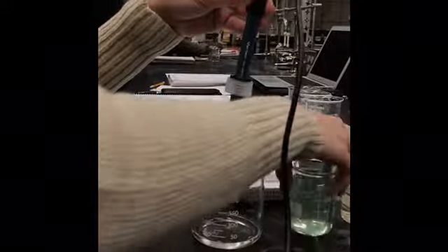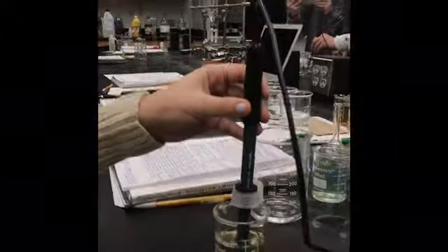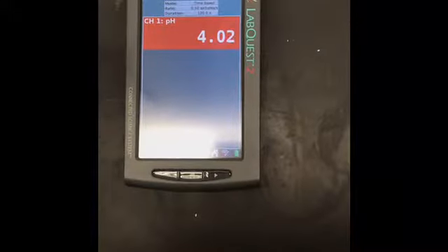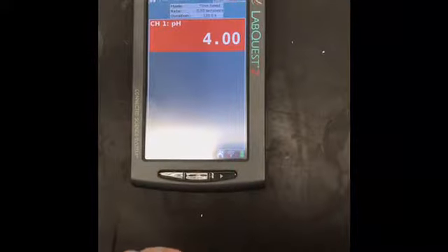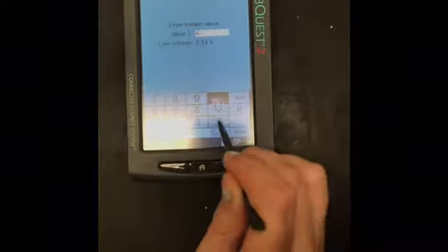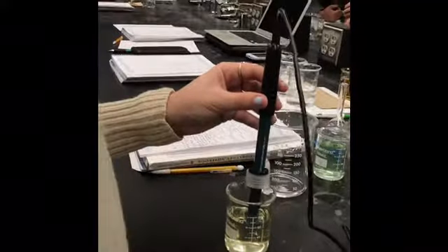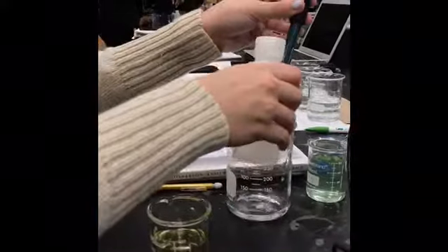Next, you will follow the same procedure for the pH 4 buffer, except you will type in 4.0 as your calibration pH. To recap, press Sensors, then press Calibrate, then press CH1, 1 point calibration, calibrate now, type in 4.0 for your new pH for your new buffer, then hit Keep, OK, and you will see that the meter reading is now 4.0. Remove the probe from the 4.0 solution and rinse with distilled water again, as you will every time it comes into contact with a new solution.